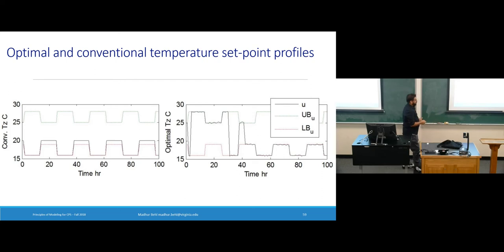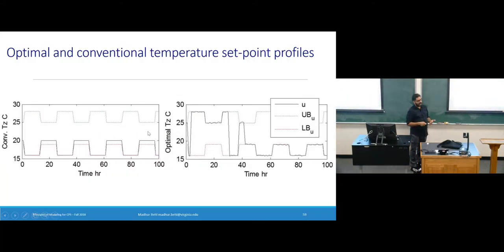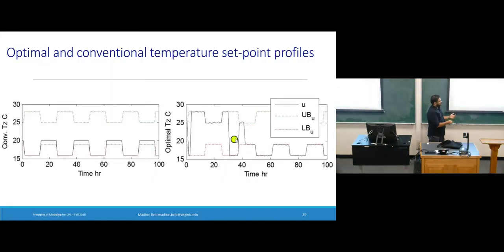What's shown here is that anytime the zone is occupied, your temperature is more or less around 20 degrees because of the HVAC function. So if you train a model to predict zone temperature with this setup, it will always just want to predict 20 degrees. Unless some new facilities manager comes and changes the set point, your model has no idea how to react outside of this 20 degree range. So what we end up doing is design an excitation signal - this black line - which has more of a design to it rather than always being at 20.